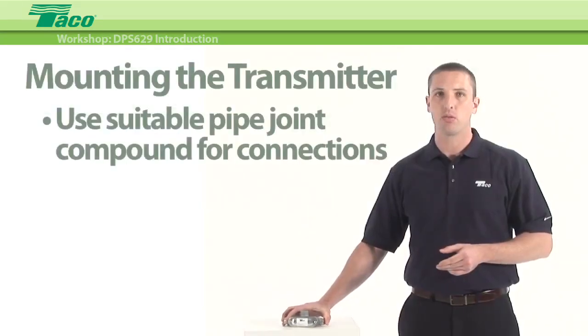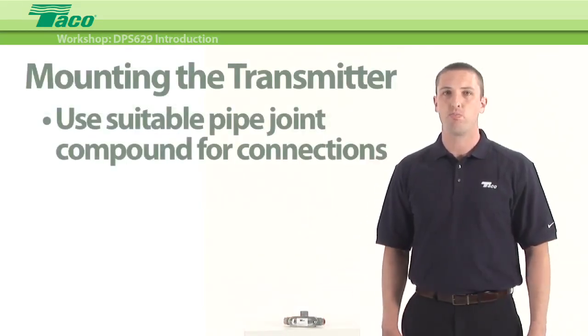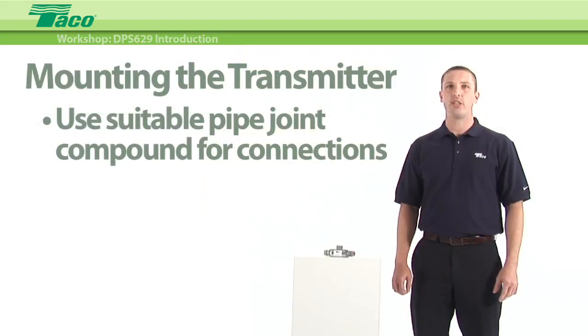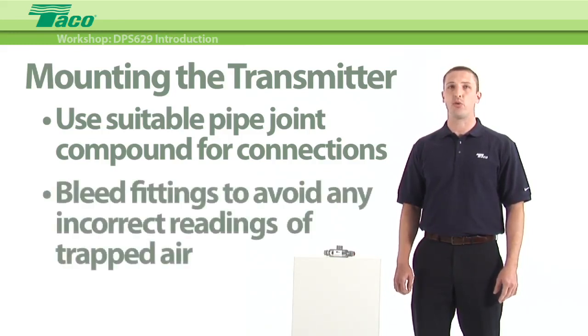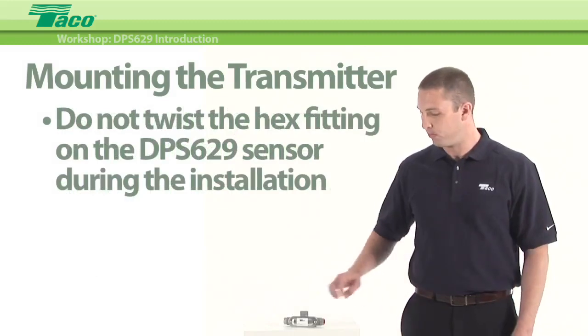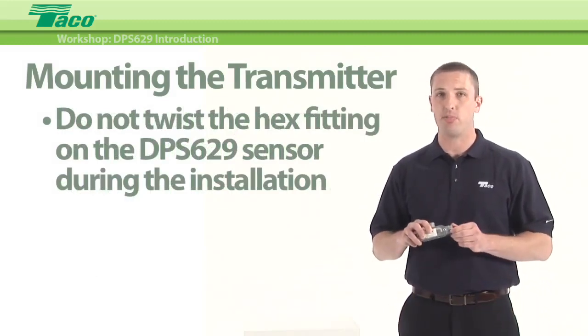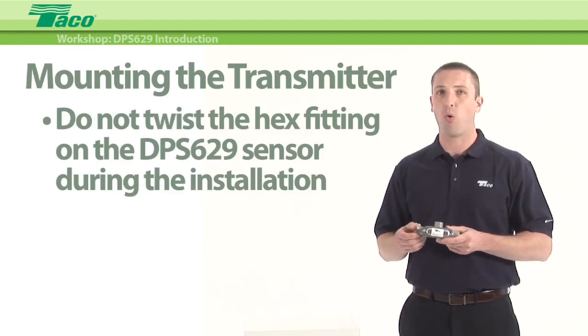Use pipe thread sealant tape or other suitable pipe joint compound when making connection to the pressure source. Avoid excess sealant which could block the pressure passage. When monitoring liquid pressures, air trapped in lines can cause incorrect readings. Bleed fittings or similar mechanisms should be used to bleed off any trapped air. Warning: torque on the hex fittings may damage the sensor. When installing, put a wrench on the fitting to hold in place while tightening piping so that the sensor is not over-torqued in the housing.